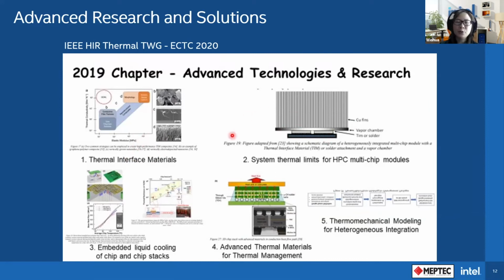The second area the team looked at is available thermal solutions and system thermal limits for high performance computing multi-chip modules. At a high level, we see up to 100 watts per centimeter square cooling capability using air cooling with vapor chamber. Moving to liquid cooling, we see close to 500 watts per centimeter square for direct water jet impingement, single phase liquid cooling. The ultimate cooling limit seems to be close to 800 watts per centimeter square using direct water cooling with silicon microchannels, from a paper published in 1981 by Tuckerman. Those are the system limits.